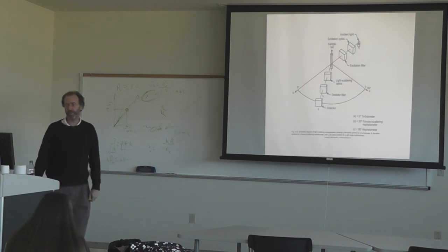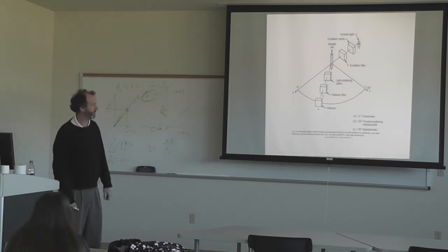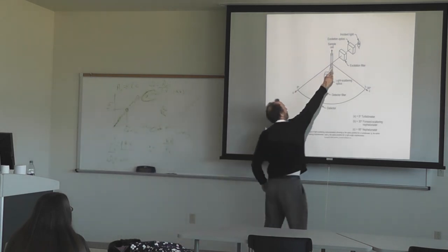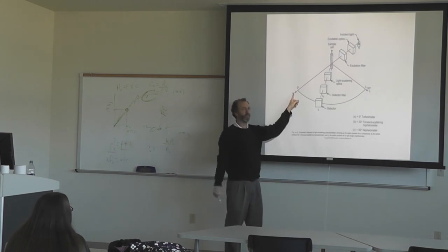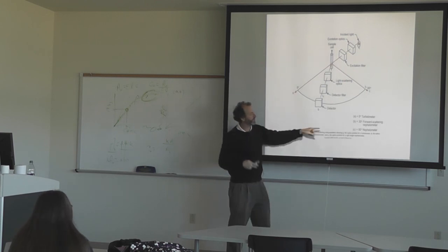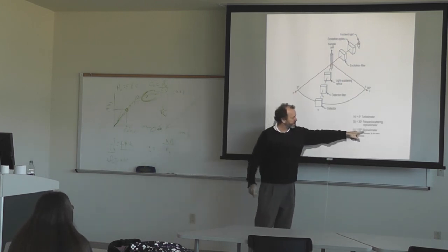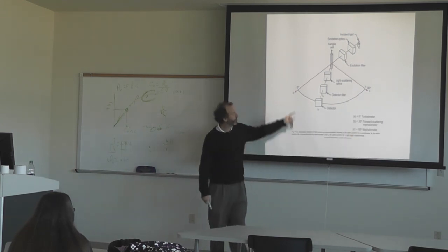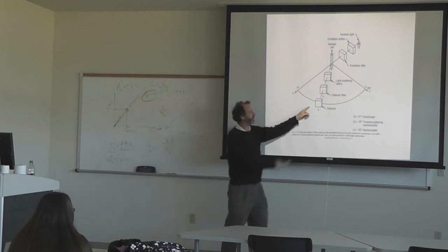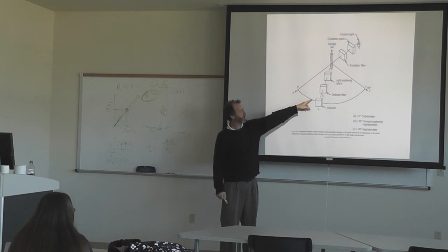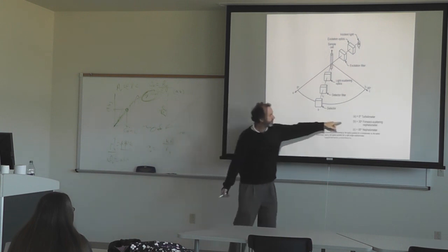With turbidimetry, you can use regular spectrophotometers to measure the turbidity, and you're looking at how much incident light is reduced. Whereas this is the important thing to know: in nephelometry, instead of using a normal spectrophotometer, you're measuring the light typically at 90-degree angles, though some have forward scattering nephelometry at 30 degrees.